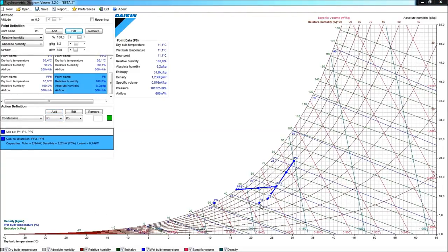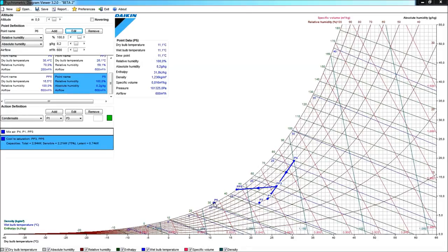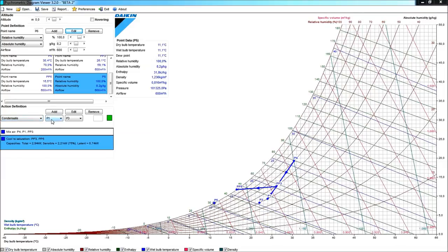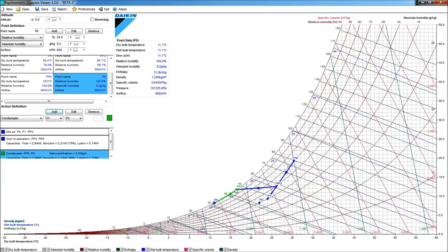So, my desired room condition, P3, it has a condition that has an absolute humidity of 8.2 grams per kilogram, so I need to specify a new point, P5, that will have the same amount of absolute humidity, and that will have 100% relative humidity. This means that it will lay on that saturation line. So, here absolute humidity, 8.2, 100% relative humidity, and the amount of air will be, of course, the amount of air behind that mixing condition, so 600. I have to condensate between the point PP5, that's my next action, towards the point P5, and I give this a green color, so when I add here, we'll have this green line pointing towards P5.